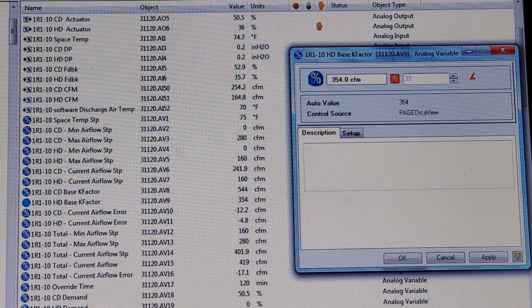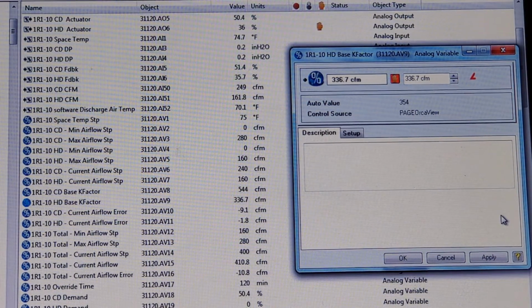So once you put that in, you'll notice the CFM will start adjusting. So look at that AI51 point, which currently reads 164 CFM. It'll average each reading, so it slowly starts to adjust down, and you should see it slowly start to adjust to what we had traversed, which was that 156.